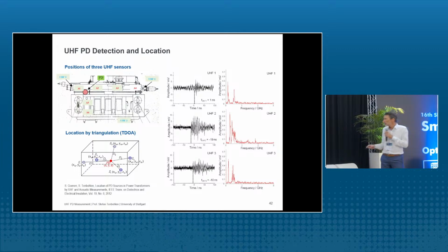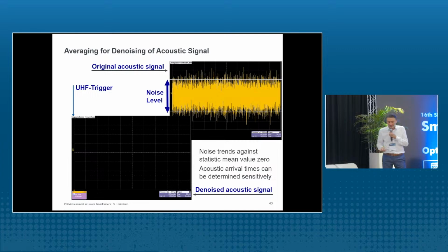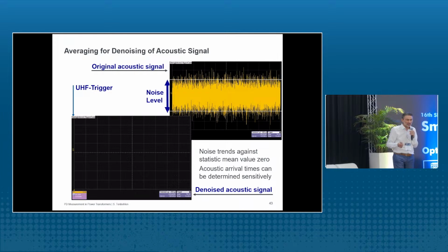And then we installed microphones on the tank wall of the transformer to measure the acoustic emissions. Problem with acoustic emissions is that the signal is very, very low. So if you do not know where the PD is, you will never find the correct positions for your microphones. But in this case, due to the location with UHF, we knew approximately where it is, and then we measured acoustic signals. Here, you can see such an acoustic signal. And what you can see here is noise.